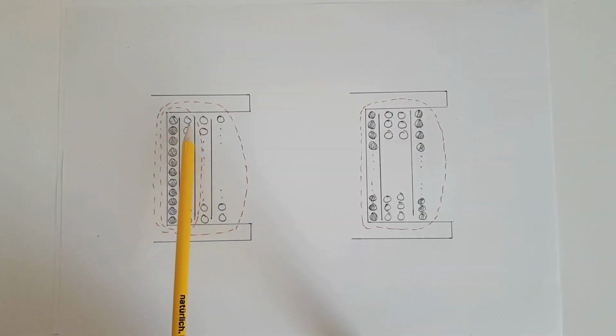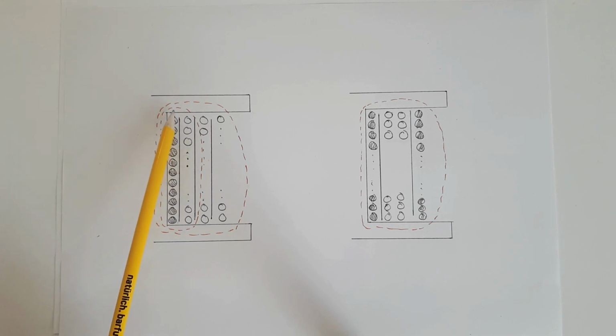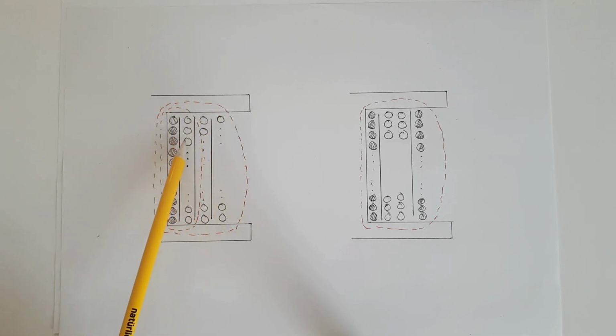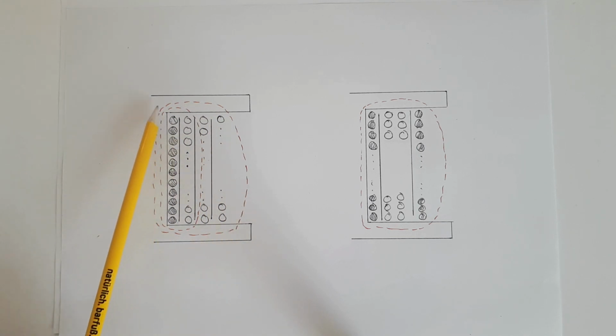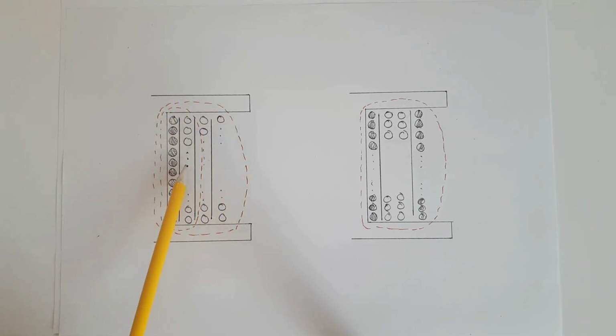When you come to put your secondary windings on, usually the transformer will contain more than one secondary winding. If that's the case, the secondary winding which contains the most power should be closest to the core. Now here you can see I've drawn the magnetic fields in red, and this magnetic field line goes all the way outside and encompasses all the windings which are inside it.